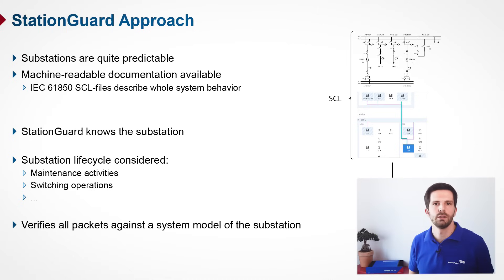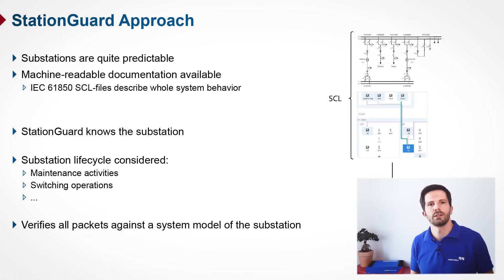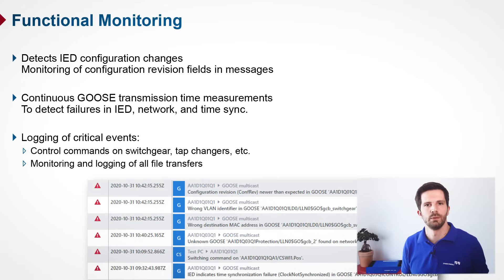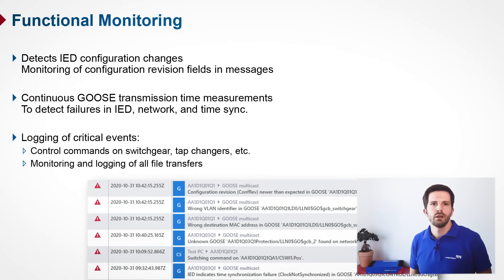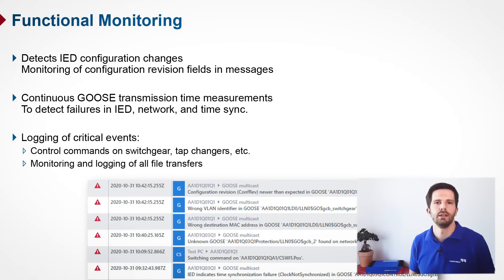The whole substation lifecycle can be considered in this system model — for example, maintenance, switching operations, and routine protection testing are already accounted for. What is especially interesting is that Station Guard not only compares and detects cyber threats, but verifies all communication against the system model, which also allows detecting functional problems. This brings us to functional monitoring: Station Guard can detect configuration changes in IEDs by monitoring the specific configuration revision fields in messages.